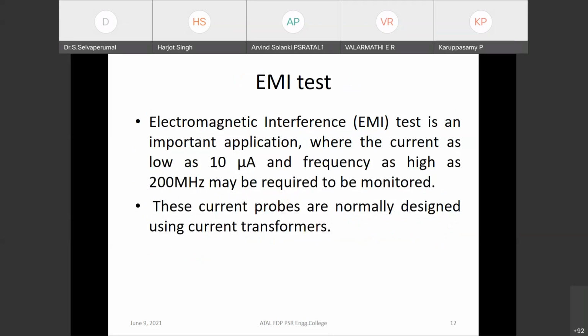The EMI test. So electromagnetic interference test is an important application where a current as low as 10 microamps and a frequency as high as 200 megahertz may be required to be monitored. So these current probes are normally designed using current transformers. Right. Next slide.